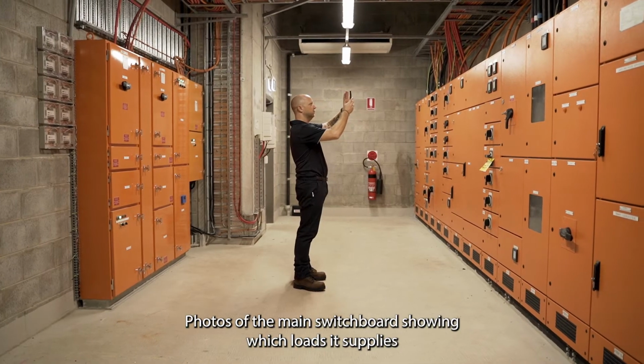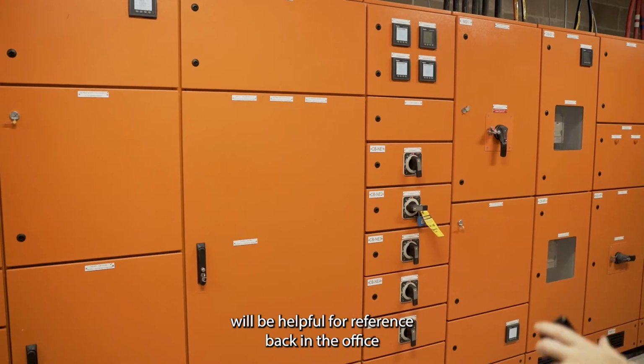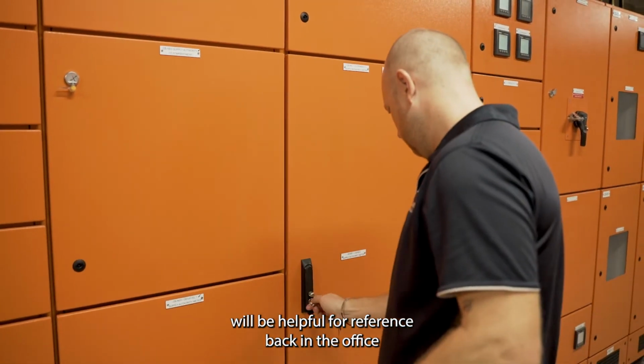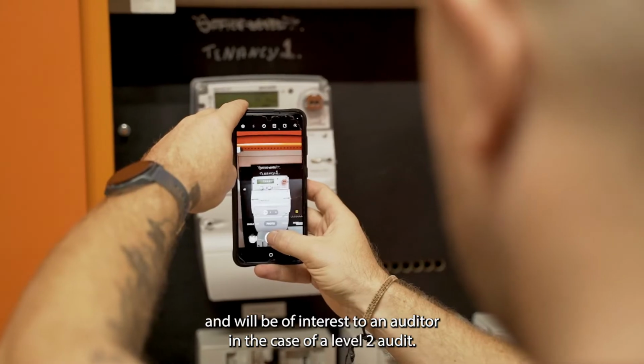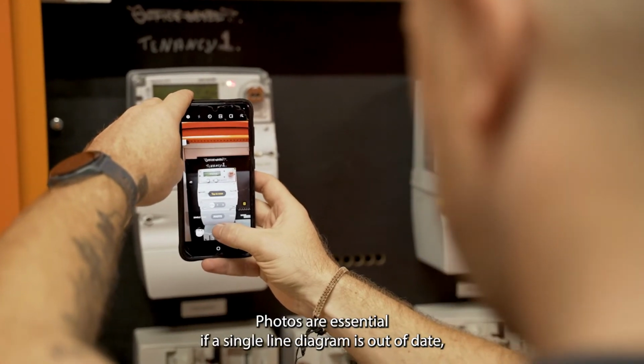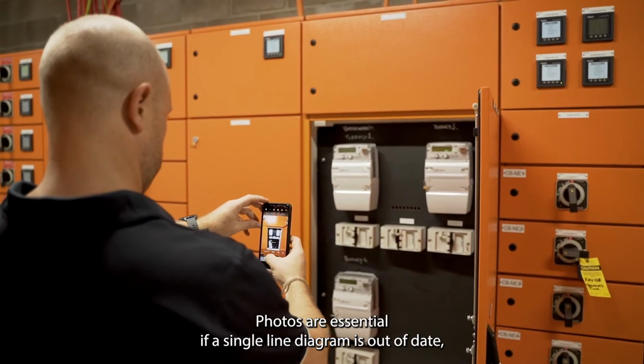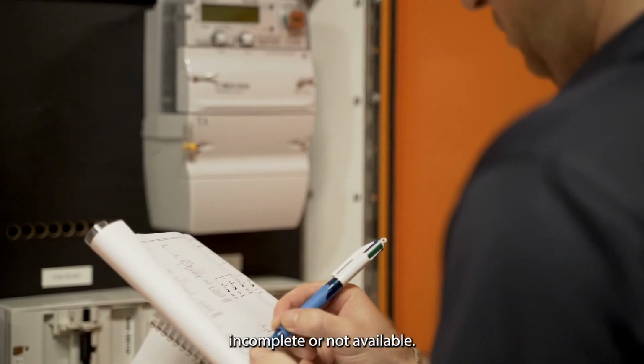Photos of the main switchboard showing which loads it supplies will be helpful for reference back in the office and will be of interest to an auditor in the case of a Level 2 audit. Photos are essential if a single line diagram is out of date, incomplete, or not available.